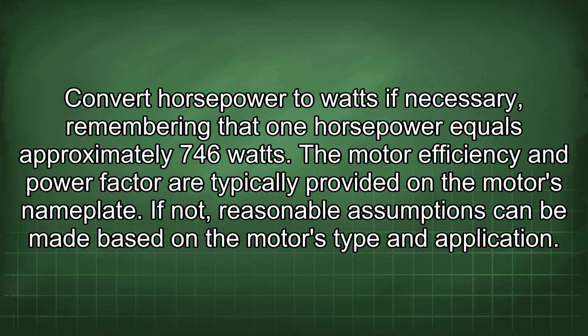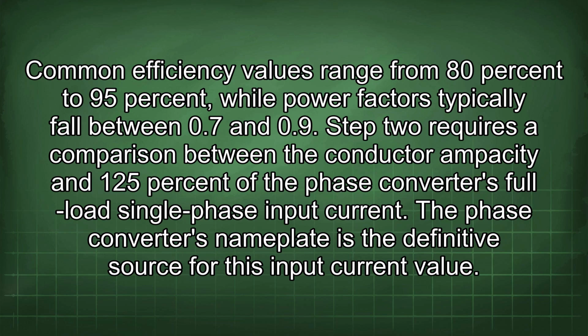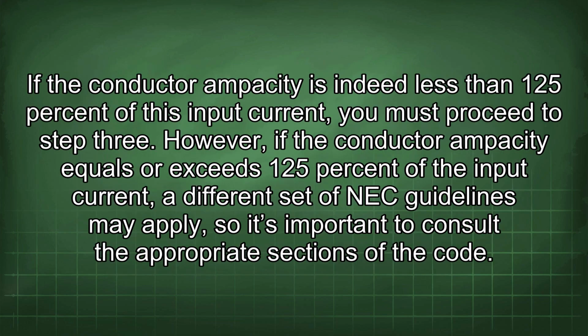The motor efficiency and power factor are typically provided on the motor's nameplate. If not, reasonable assumptions can be made based on the motor's type and application. Common efficiency values range from 80% to 95%, while power factors typically fall between 0.7 and 0.9. Step 2 requires a comparison between the conductor ampacity and 125% of the phase converter's full load single-phase input current. The phase converter's nameplate is the definitive source for this input current value. If the conductor ampacity is indeed less than 125% of this input current, you must proceed to step 3.